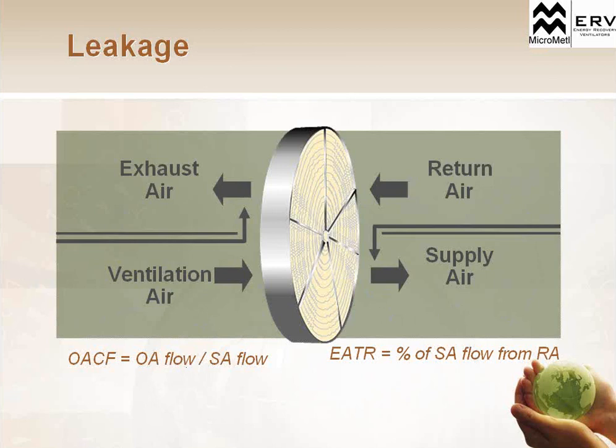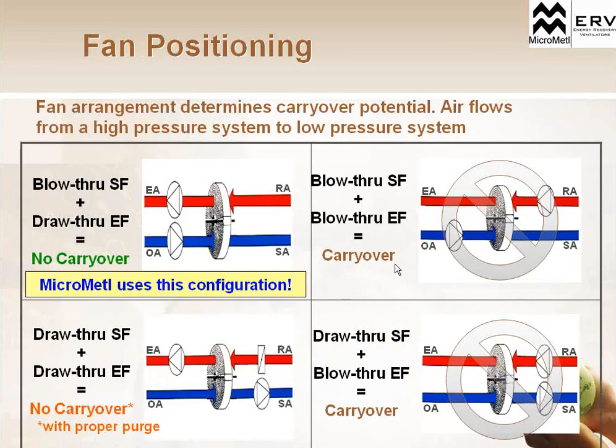Conversely, we can get outside air that is coming in from the space. It doesn't want to go through the wheel, and it can actually go back into the exhaust air. So that fresh air is just going to go back and be exhausted from the building instead of going through that wheel. And that's because of these blower arrangements. The ideal blower arrangement is going to be a pull-through and a push-through design. If we're pulling the airflow across that wheel, it's going to be less likely to go down on the other side of that wheel, that exhaust air from the building coming out. So we're going to pull it through the wheel, and at the same time, we're going to push air into the system, which isn't going to draw that air.